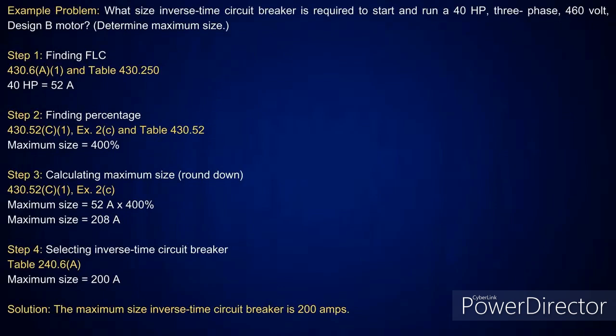Then I go to my inverse time circuit breaker. I come down and pick up exception 2C. It says I can take it at 400%. So 52 amps at 400% is 208 amps. Once again, it says I can't exceed the calculated value, so I drop down to the next standard size, which is 200 amps.